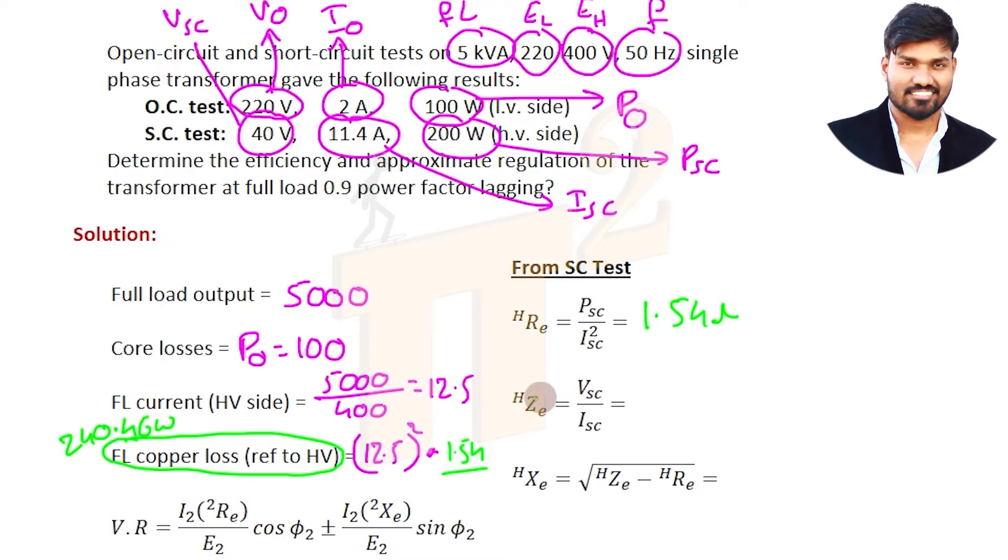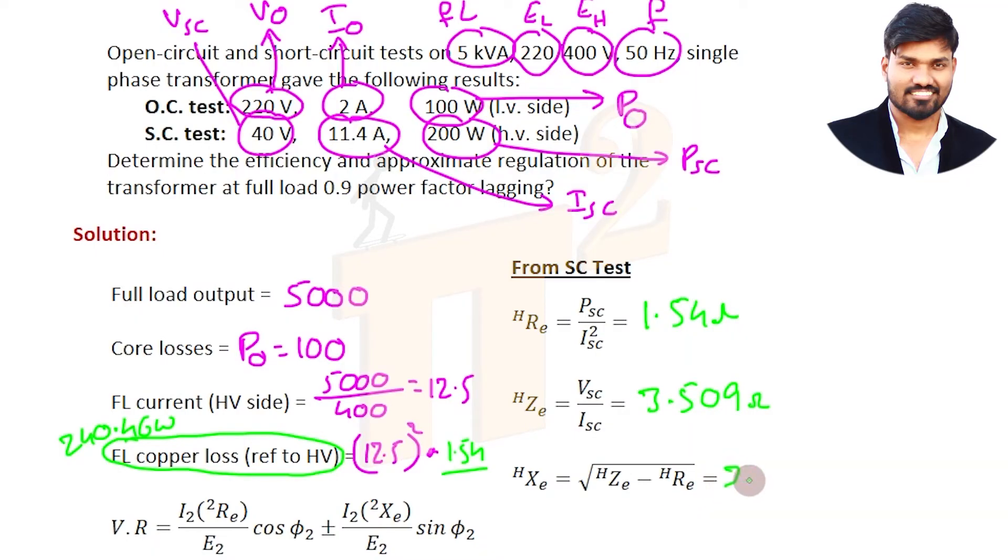Next comes Z_EH which is V_SC by I_SC, 40 by 11.4. This is Z_EH. Then X_EH just go for square root of 3.51 squared minus 1.54 squared. So X_E is 3.152 Ohms. We filled up this table.